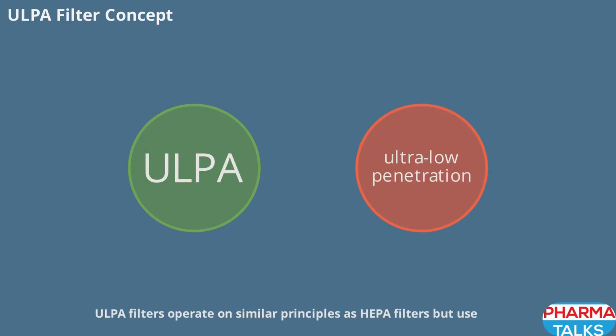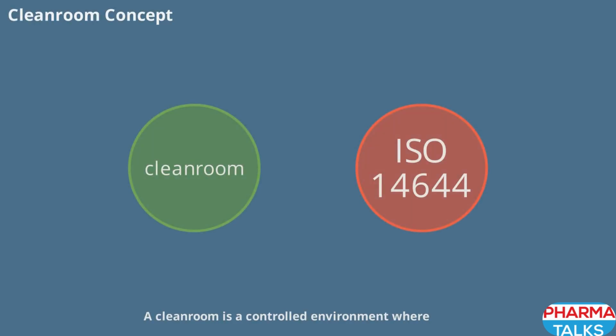ULPA filters operate on similar principles as HEPA filters, but use even finer fibers and a denser structure to capture smaller particles. Their advanced design allows them to achieve ultra-low penetration rates, making them suitable for the most demanding cleanroom environments. However, this also means they require more energy to push air through, impacting overall system efficiency. Cleanroom is a controlled environment where the concentration of airborne particles is strictly regulated.